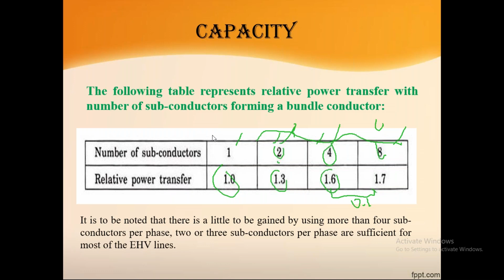So this is the capacity of bundle conductors based on how many subconductors are used in that conductor. If they are using two subconductors in the bundle, its capacity is 1.3. If they are using 4, it is 1.6. If they are using 8, its capacity is 1.7. So this is the table reference for the capacity and power transfer rating of a conductor and bundle conductor. It is already said here that 2 or 3 subconductors per phase are sufficient for most of the EHV lines. So most extra high voltage lines prefer 2, 3 and 4 conductors. So this is the capacity point of view of bundle conductors.